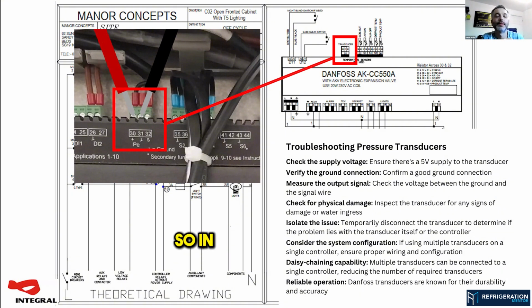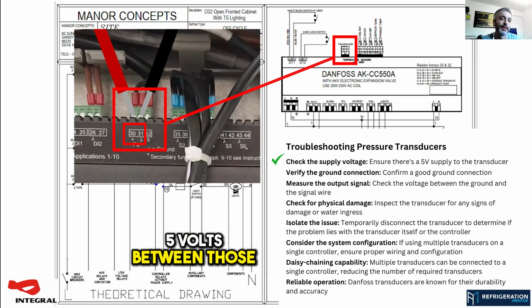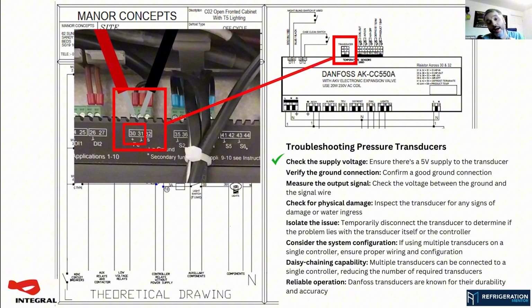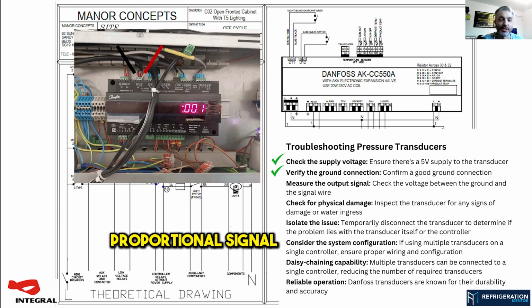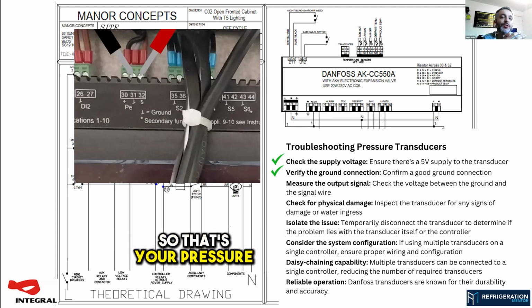Yeah, of course. So in this application right here, this is one controller with one transducer. They're all ratiometric 5-volt transducers. So they need a supply, a ground, and they give you a voltage back. So 30 and 31 there is your supply and your ground, which you've got the probes on. So you should see 5 volts between those two DC. If you go between ground and S with your probes, you will see the proportional signal back. So that's your pressure reading effectively.